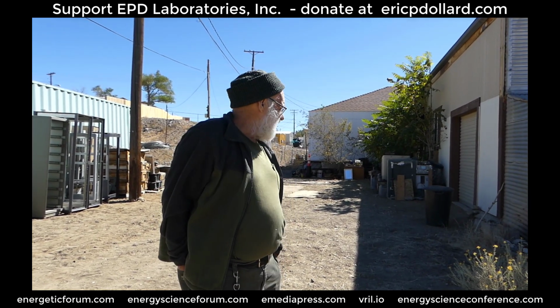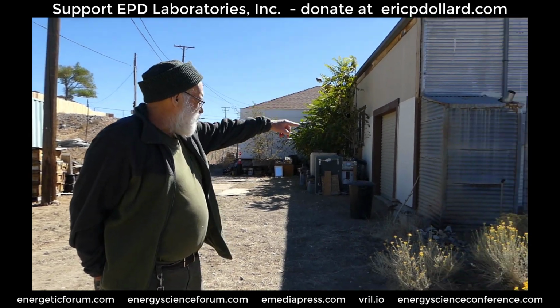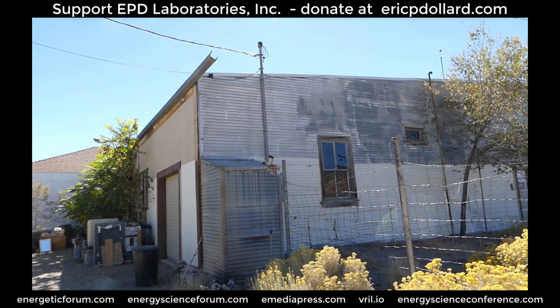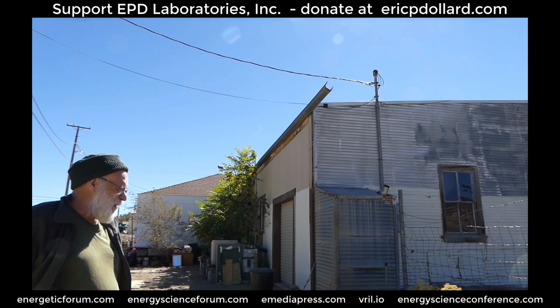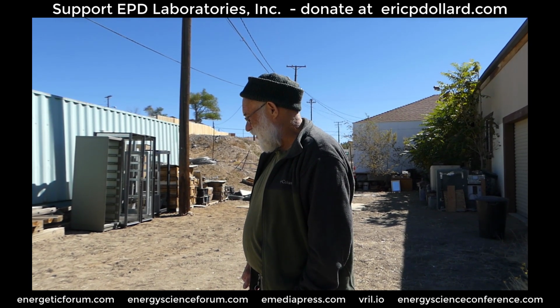So NV Energy wants about $30,000 to put that pole in with the transformers, and then it would probably be another $3,000 or $4,000 to change the service entrance from 220 to 440. And I can't say what it's going to cost right off, but it seems to me it's going to be about $30,000 at least in the building for all the panel boards, and then the extensive distribution system to carry the power everywhere. So that's one of the biggest cost items here, is to get the electrical, and then the next down is to get all the walls up in the building, and then down from that is the ventilating system. And how much all that's going to come up to, I can't really say, but it's going to be in the $100,000 bracket. Okay. So I guess we can go in the trailer, or container more properly.